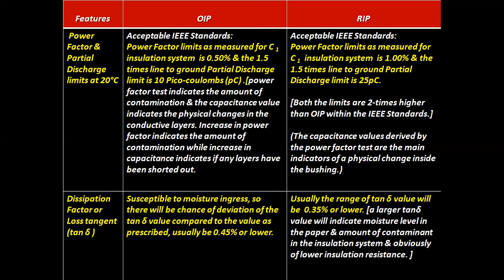Acceptable IEEE standards for RIP bushings: the power factor limit as measured for the C1 insulation system is 1%, and the 1.5 times line to ground partial discharge limit is 25 picocoulombs. Both limits are 2 times higher than OIP within the IEEE standards. The capacitance value derived by the power factor test is the main indicator of a physical change inside the bushings.